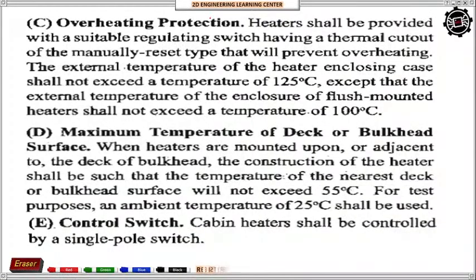Okay, overheating protection. So heater shall be provided with suitable regulating switch having a thermal cutout, no, of manually reset type that will prevent overheating. So the external temperature of the heater enclosing case shall not exceed 125 degrees, except that the temperature of the enclosure of flush-mounted heater shall not exceed 100 degrees Celsius. No, kapag sa deck naman or bulkhead, so 55 degrees Celsius. No, at yung ambient temperature is 25 degrees Celsius.